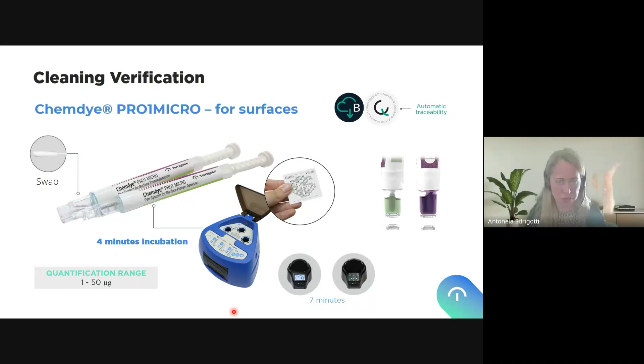So which are the tips for a correct cleaning verification test by using a quantification protein test? Write clear and detailed instructions for use to ensure reproducible standard operating procedures, to make sure that we can reproduce the results. We need to compare. If we want to use a protein test, we have to be sure that every time we do the test, we do it in the same way. We have to standardize the frequency and respect it.